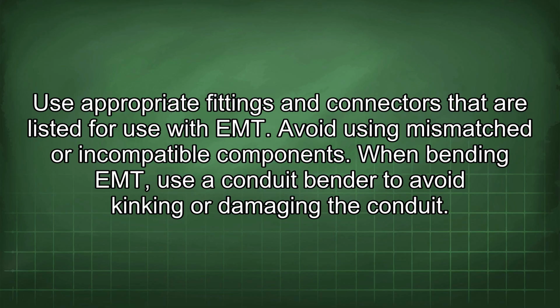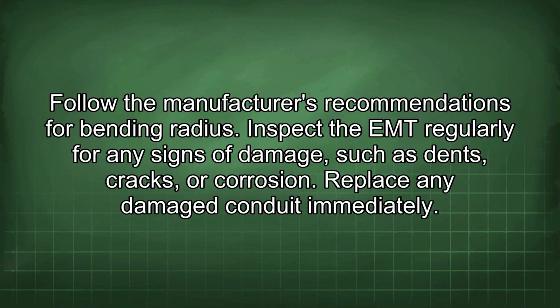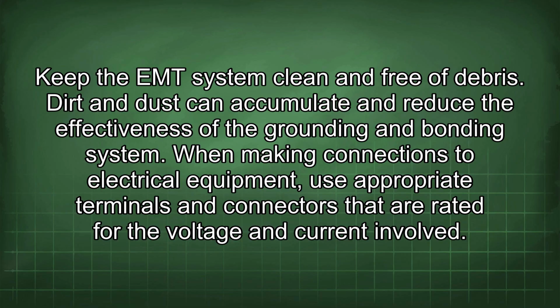Avoid using mismatched or incompatible components. When bending EMT, use a conduit bender to avoid kinking or damaging the conduit. Follow the manufacturer's recommendations for bending radius. Inspect the EMT regularly for any signs of damage such as dents, cracks, or corrosion. Replace any damaged conduit immediately. Keep the EMT system clean and free of debris. Dirt and dust can accumulate and reduce the effectiveness of the grounding and bonding system.